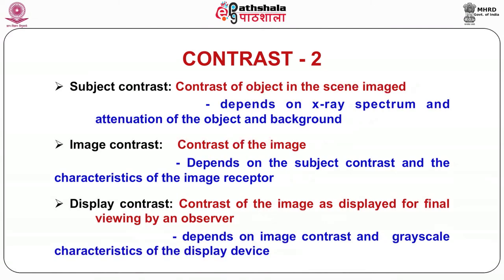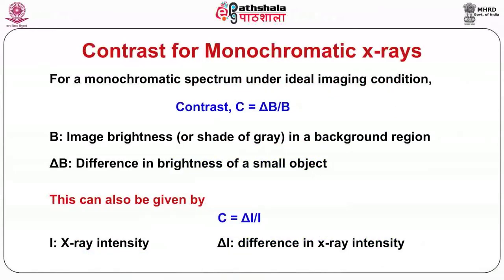Image contrast depends on the subject contrast and the characteristic of the image receptor, that is the detector. The contrast of the image as displayed for final viewing by an observer is display contrast, which depends on image contrast and the gray scale characteristic of the display device. For a monochromatic spectrum under ideal imaging conditions, contrast C is equal to the ratio of delta B upon B, where B is image brightness or shade of gray in a background region and delta B is the difference in brightness of a small object. This can also be given as C equals delta I by I, where I is X-ray intensity and delta I is the difference in X-ray intensity.